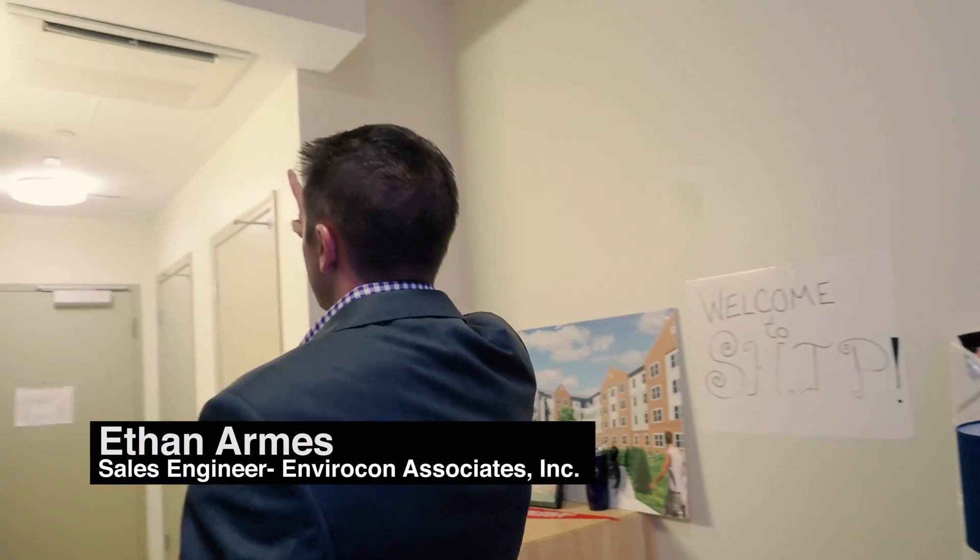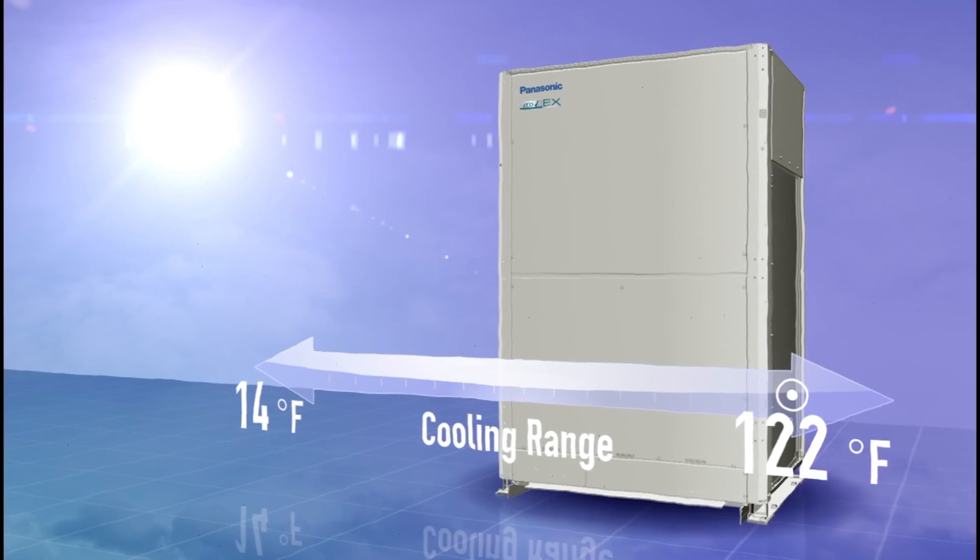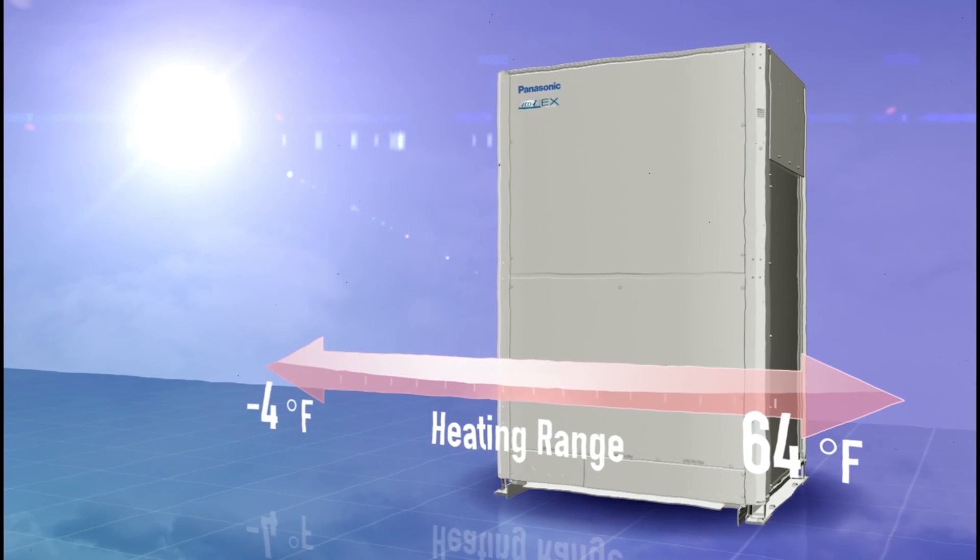The students were more satisfied. Even on a day like today where it's 15 degrees outside, the indoor unit is still capable of supplying sufficient discharge air temperature to maintain room set point. The first year we were skeptical, but we found that these units can meet temperatures down to zero degrees — they're capable of scrubbing heat out of the cold air and satisfying the rooms.